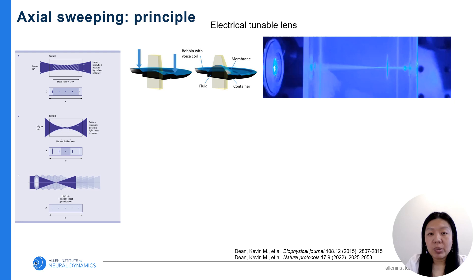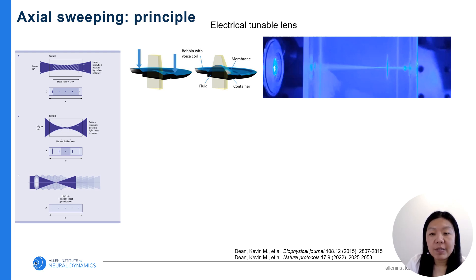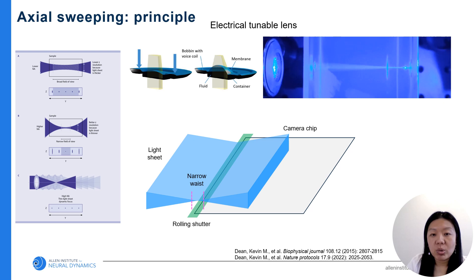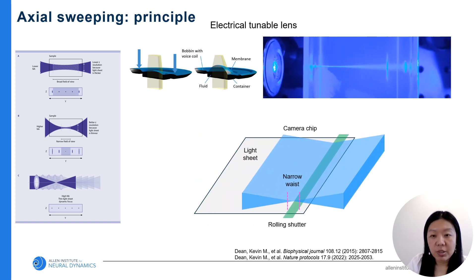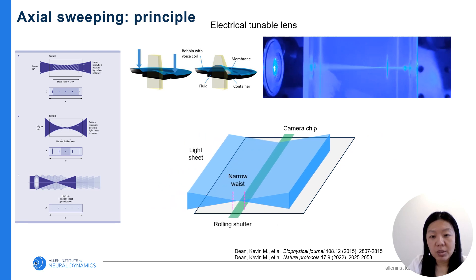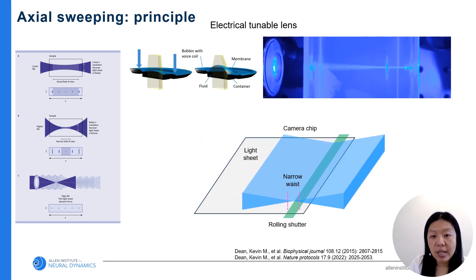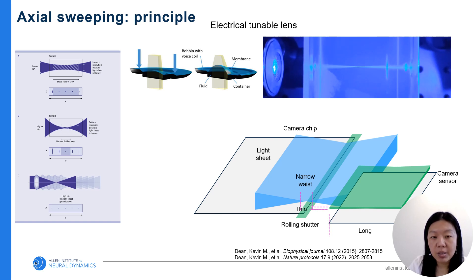As we see from the light sheet principle illustration, to achieve high Z resolution the NA of the illumination beam is higher, which means only a small zone of the sheet is actually in the focus zone. To achieve higher resolution through the entire field of view, Kevin Dean and colleagues introduced the idea of axial sweeping. An electrically tunable lens (ETL) is one way to shift the focus of the sheet. A camera with a rolling shutter allows only a certain number of line pixels to be active at one moment, and synchronizing the ETL with the rolling shutter creates an artificially thin sheet on the imaging sensor.